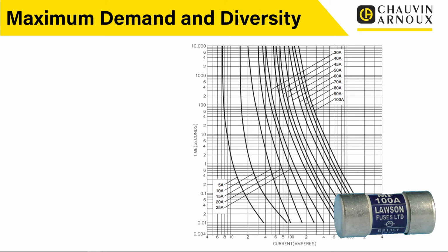So it's almost like we've got 2 installations joined together. At the bottom there, we go for 200 amps and we follow that up until it crosses the 100 amp curve. Then we go across to the left, and you will see that we hit 400 seconds. So just exploring that logic, if we overload the installation with a BS1361 100 amp fuse at 200 amps, it will take 400 seconds, which I think is about 6 minutes 40, something like that, to go pop.